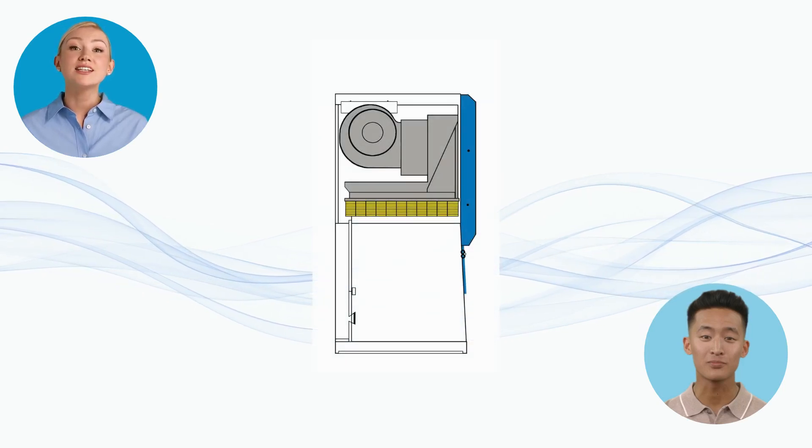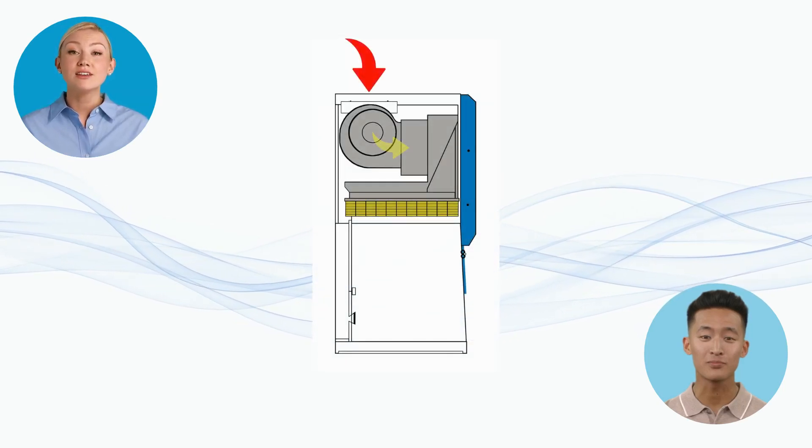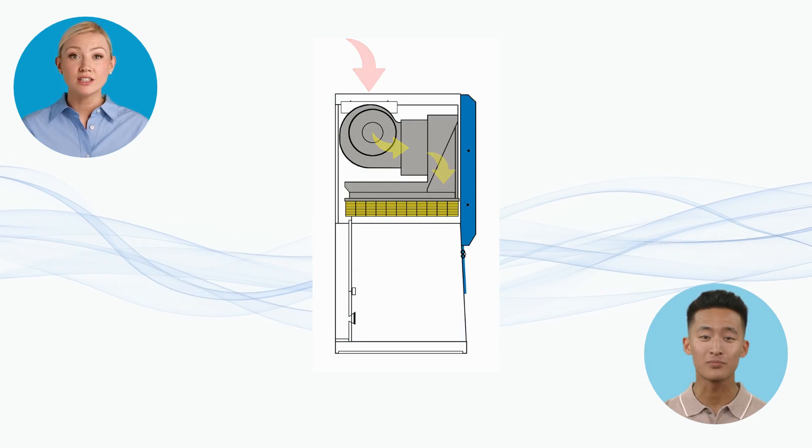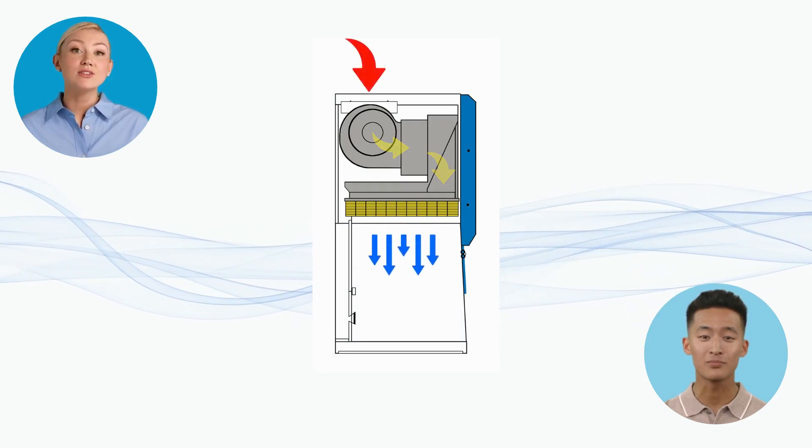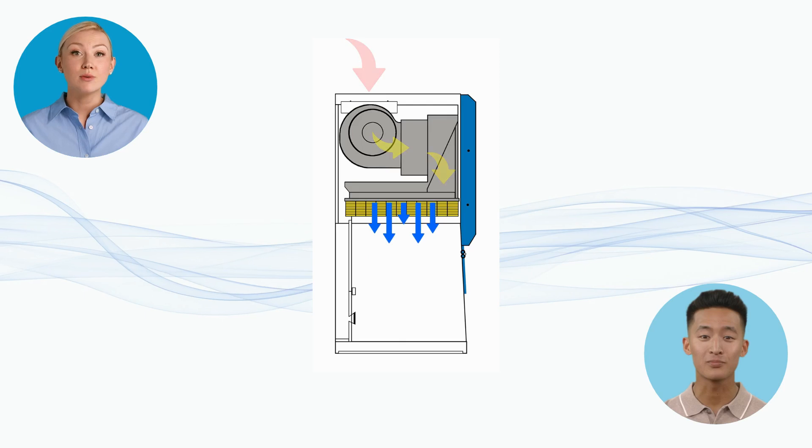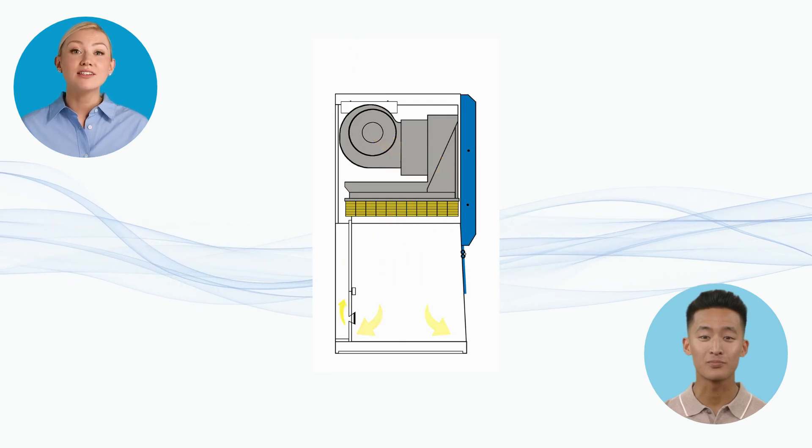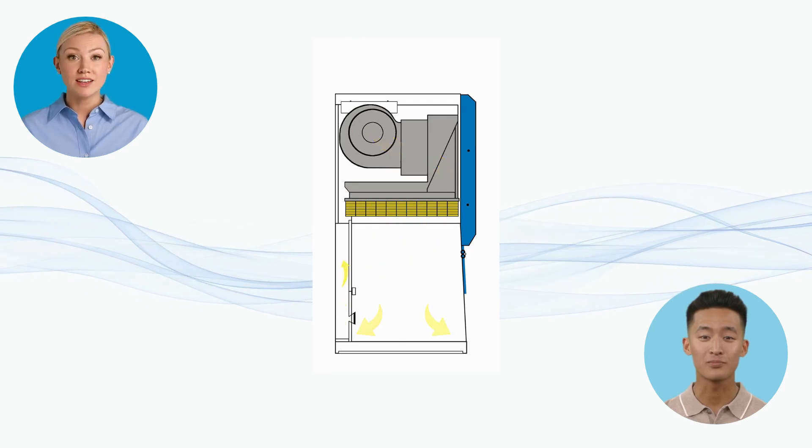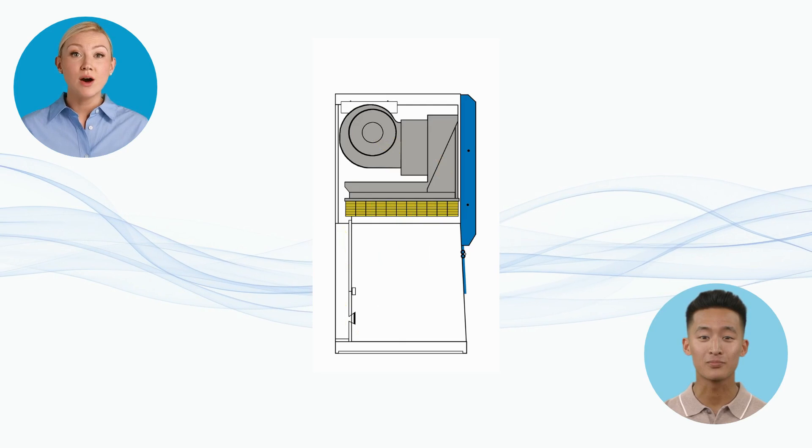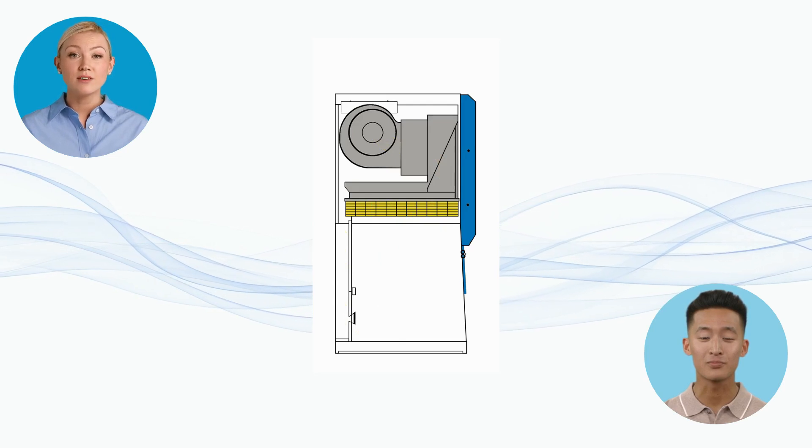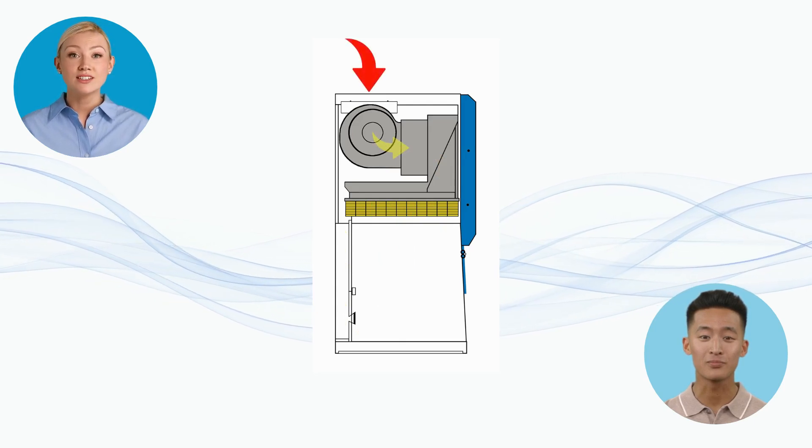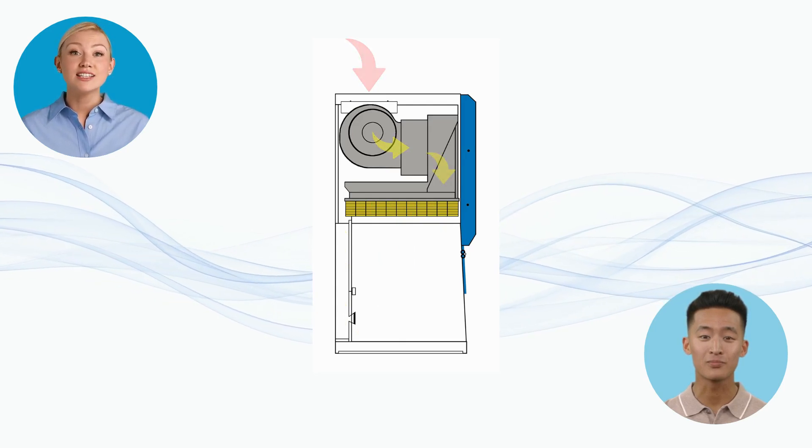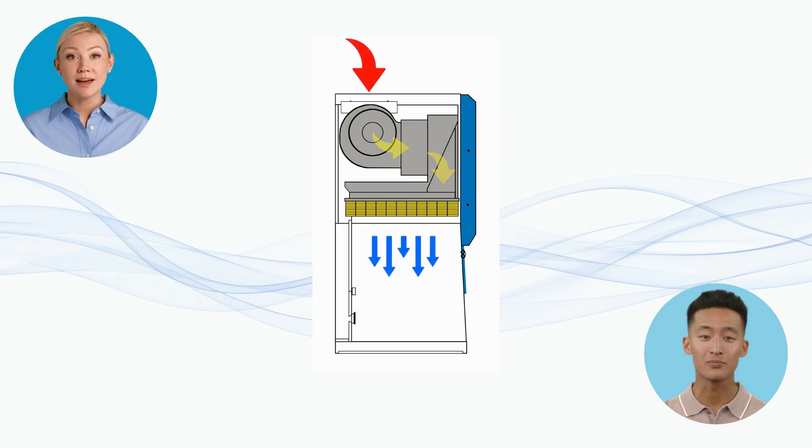So imagine we've just sliced the hood in half. This is a vertical laminar flow version. The red arrow shows where air is drawn in from the top through a pre-filter, passes through a high-efficiency HEPA filter, and then flows vertically down to the workbench. About half of the air volume is exhausted outside, while the rest is recirculated through slots at the bottom of the back panel.